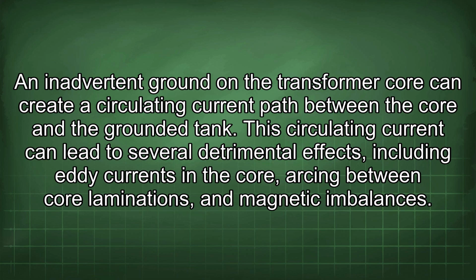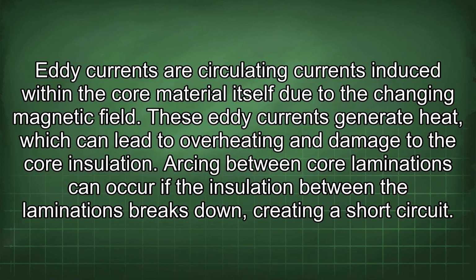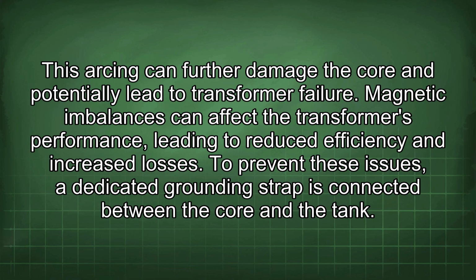This circulating current can lead to several detrimental effects, including eddy currents in the core, arcing between core laminations, and magnetic imbalances. Eddy currents are circulating currents induced within the core material itself due to the changing magnetic field. These eddy currents generate heat, which can lead to overheating and damage to the core insulation. Arcing between core laminations can occur if the insulation between the laminations breaks down, creating a short circuit. This arcing can further damage the core and potentially lead to transformer failure. Magnetic imbalances can affect the transformer's performance, leading to reduced efficiency and increased losses.